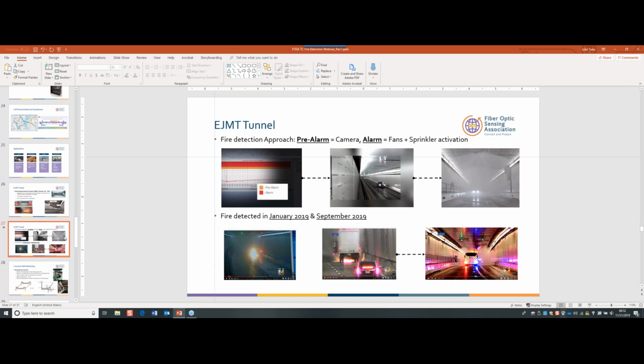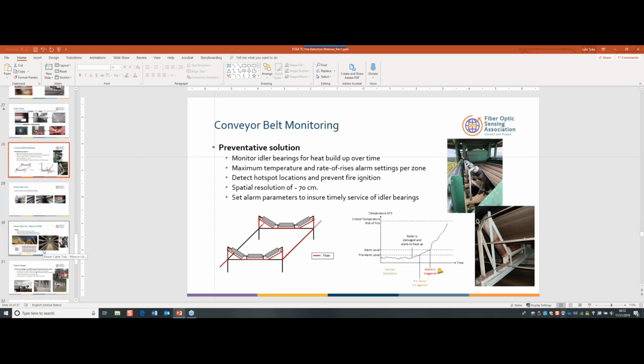So in a building context, how much fiber do you need to put in? Can you detect across the building, or do you need to be within a particular distance in order to pick up an issue? Similarly to what we discussed about tunnels and other places, you can run this fiber as simply as running a wire across a building and be able to detect a fire and know exactly what the temperature is. As long as the building is not, let's say, only 3 feet long, you'll be okay, because the spatial resolution is within a meter or 3 feet. It's very simple to run the fiber optic linear detection and be able to detect up to certain areas.